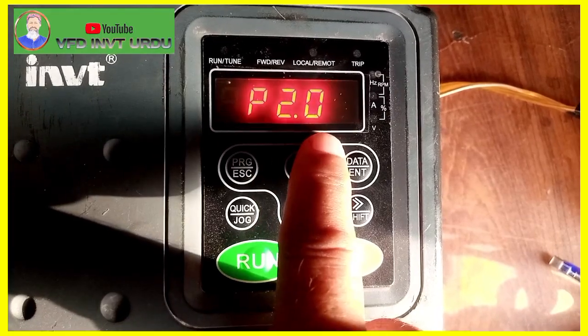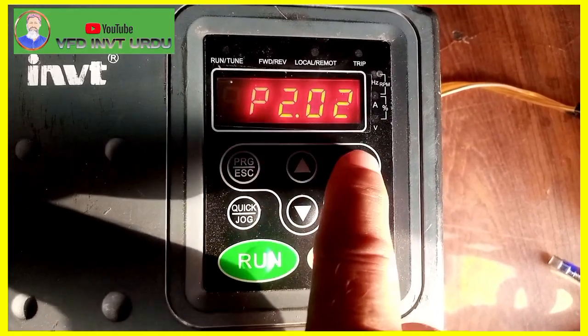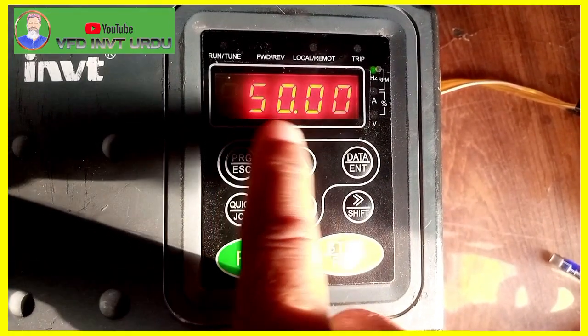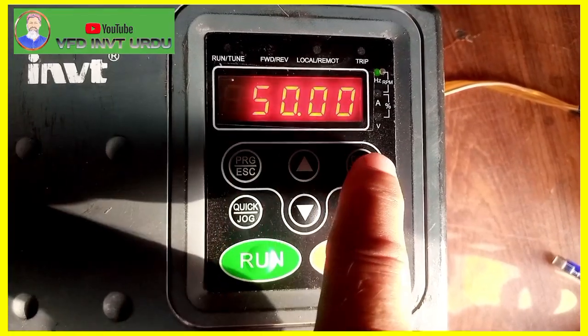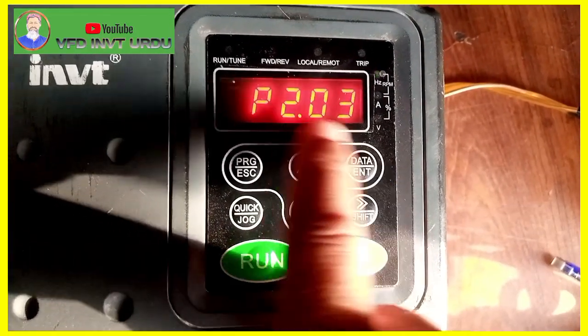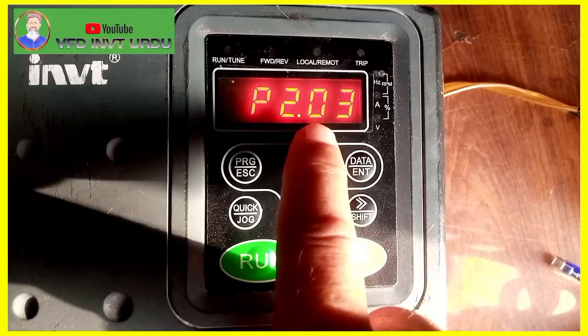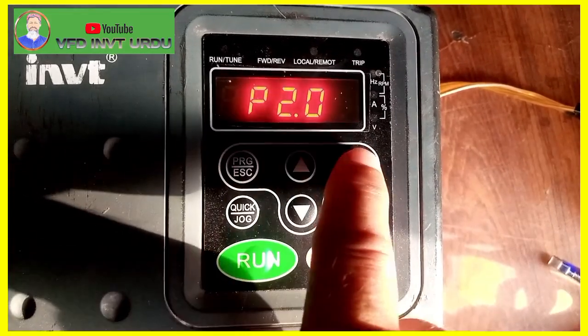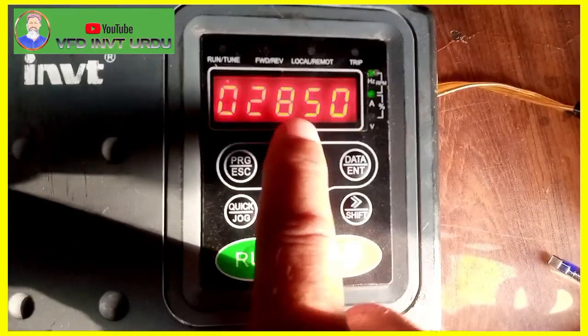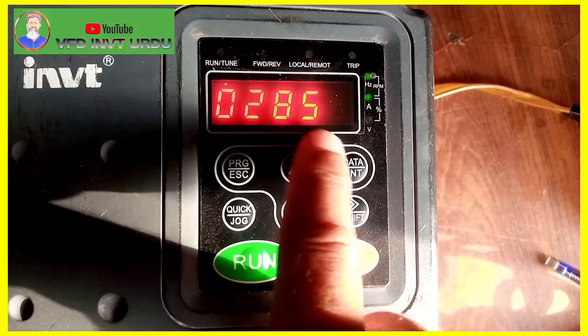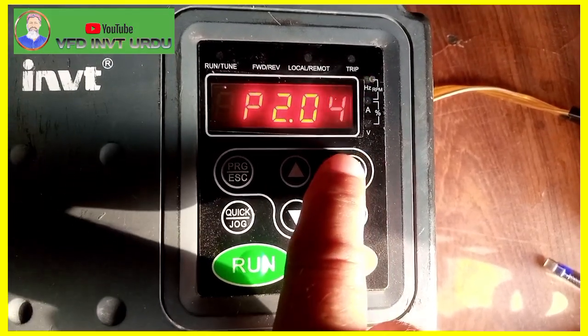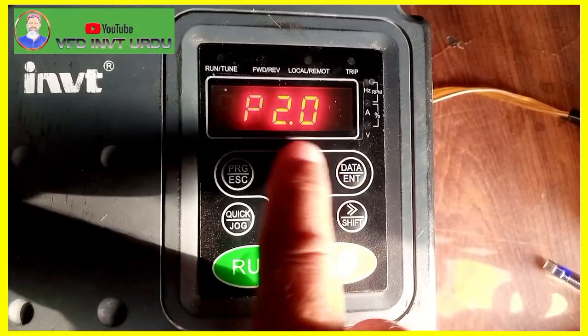P2.3. This is the motor frequency. Normally, set it to 50 Hz. Press data to confirm. P2.4. This shows the motor RPM. For example, if your motor is 2850 RPM or 1440 RPM, enter accordingly. Press data to save.